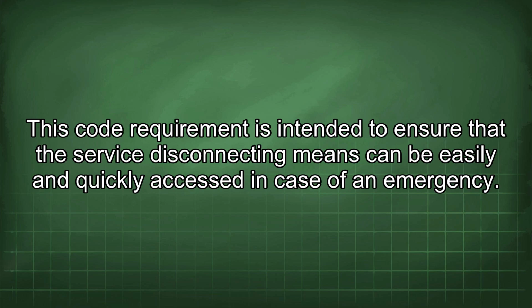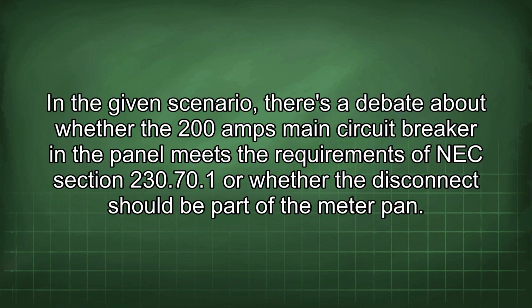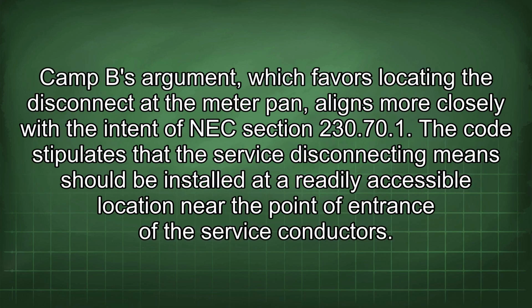This code requirement is intended to ensure that the service disconnecting means can be easily and quickly accessed in case of an emergency. In the given scenario, there is a debate about whether the 200 amps main circuit breaker in the panel meets the requirements of NEC Section 230.70.1 or whether the disconnect should be part of the meter pan. Camp B's argument, which favors locating the disconnect at the meter pan, aligns more closely with the intent of NEC Section 230.70.1. The code stipulates that the service disconnecting means should be installed at a readily accessible location near the point of entrance of the service conductors.